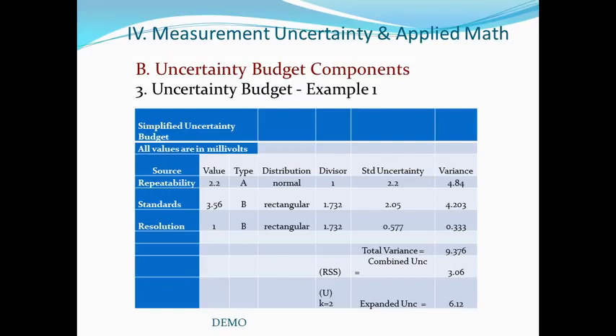and calculated some statistics. And the divisor in the next column is used to get us into a value that will be for one standard deviation. So the value 2.2 here is inferred as being calculated on the basis of one standard deviation, giving us a divisor of 1. The standard uncertainty then is calculated by taking our value, dividing it by the divisor column, or 2.2 divided by 1, gives us a standard uncertainty value of 2.2 for this line item.